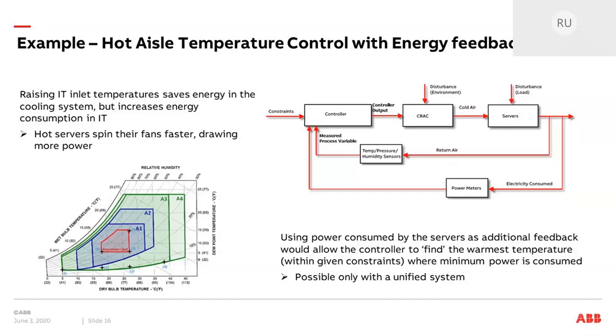Sometimes as the inlet temperature goes up, servers start to spin their internal cooling fans faster, and those fans draw a lot of power. So even though you might be saving energy overall from a cooling system perspective, your actual critical power consumption within IT is going up. If you can measure that as part of the same system, you could feed it back into your controller and make sure you're not setting the temperature set point too high.